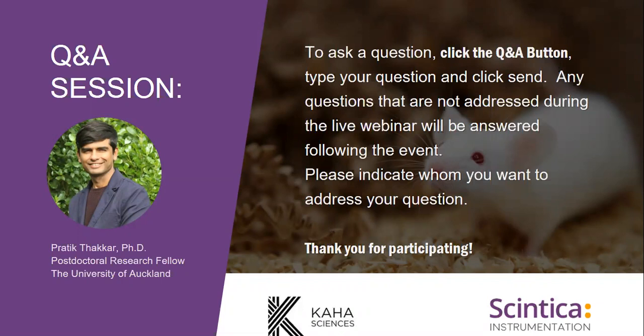Okay. Based on your graphs, one of the attendees is also asking how some of those units are converted, from PO2 to some of the other real units or pressure units. Can you talk a little bit more about that? So I think that's a very technical question, but I can give a brief answer. The recording we get is in nanoampere, and that's how the telemetry and the signal are designed to get the nanoampere signals into the computer output in the Spike software. But according to our need, that was converted into micromolar.